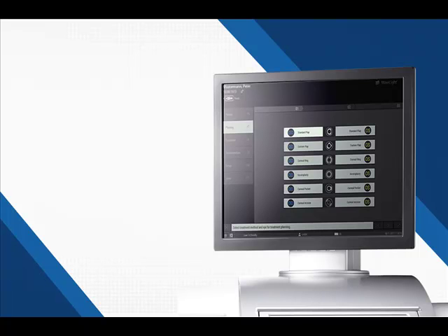So for redocking, the softfit interface need not be replaced. You can continue to use the same interface for redocking. And we're talking about seconds between applying the patient interface, aligning, approaching, securing, looking at the monitor before continuing. We're looking at seconds. In the worst case scenario, if this happened, it's a software command to stop suction. It stops instantly.